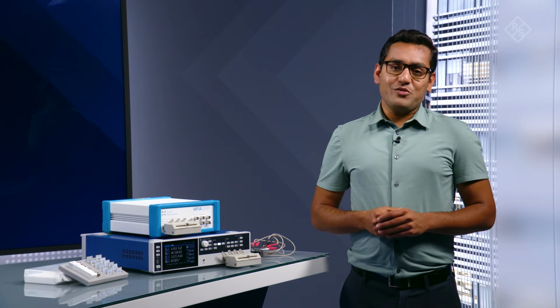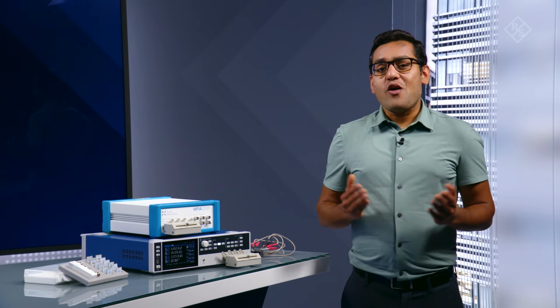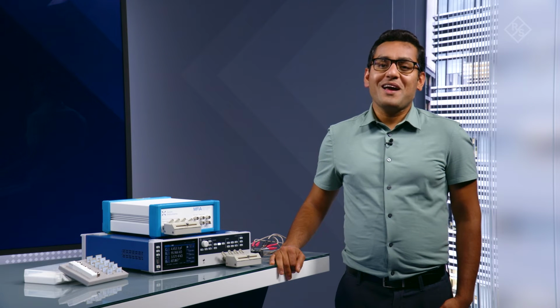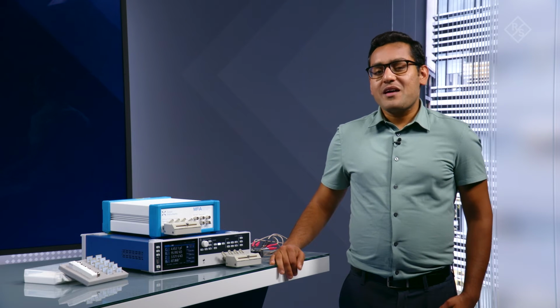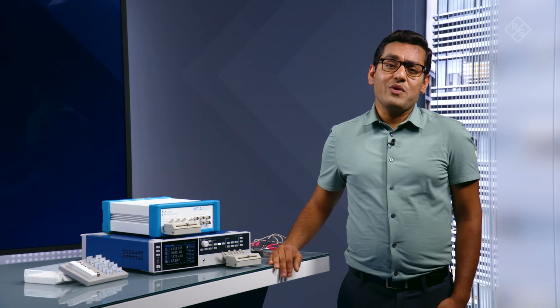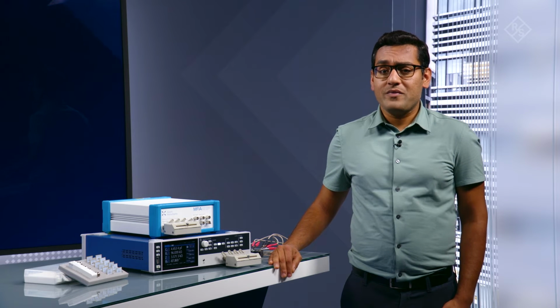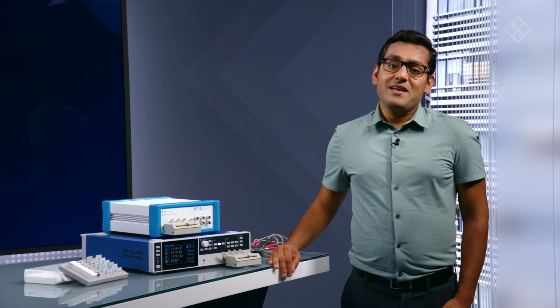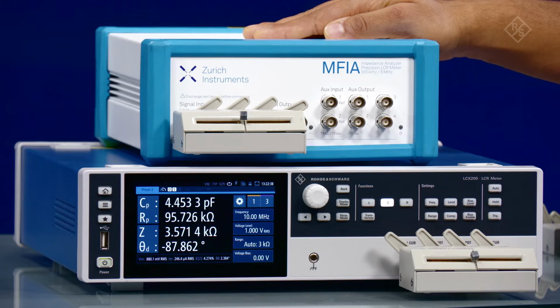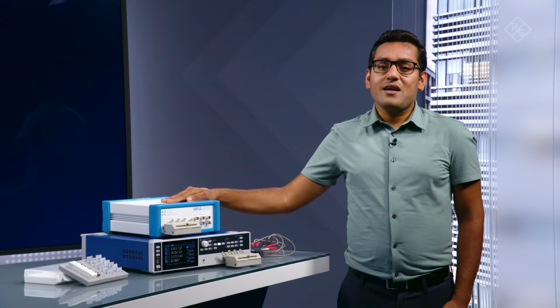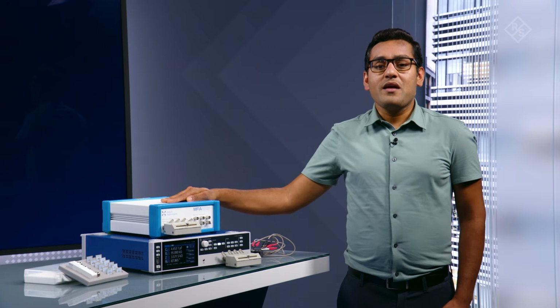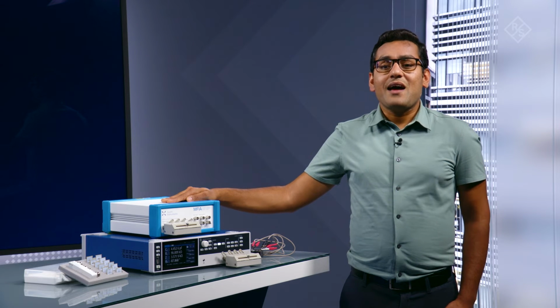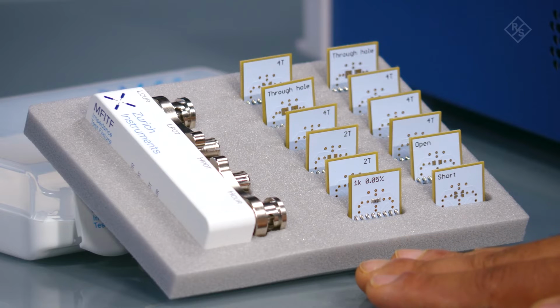LCR meters are ideal for component R&D and component testing, offering impedance measurements between 1 milliohm and 100 megaohm. However, in some cases, such as material science, impedance can be very high, sometimes even up to 1 teraohm. In such applications, the impedance analyzer, MFIA, could be a right fit for you. It also has a very high data acquisition rate and is therefore ideal for sensors and microfluidic applications. MFIA comes with LabOne instrument control software, MFITF test fixture, and MFIA-DC carrier for mounting devices.